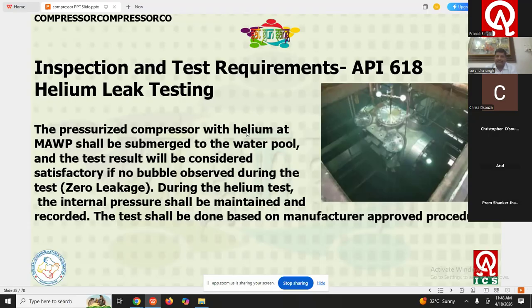So simply we fill the helium into the compressor and pack it with helium, then we submerge the compressor into the water. If any leakage is there, definitely bubbles will come out from the compressor and travel to the water surface. So we can detect any leakage. The only purpose of helium is that, since it is a lighter gas, any leakage that cannot be detected with air or nitrogen will definitely come out with helium. That's why we use helium gas in this pneumatic testing.